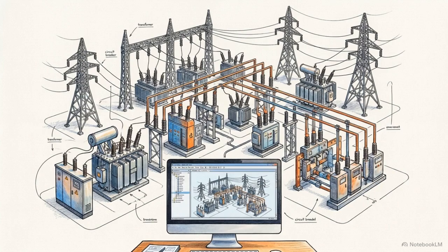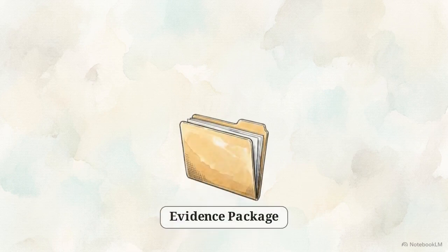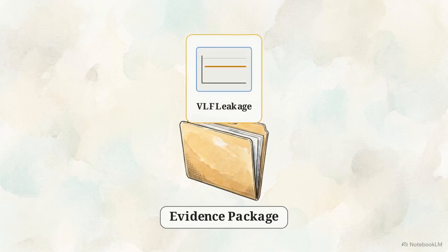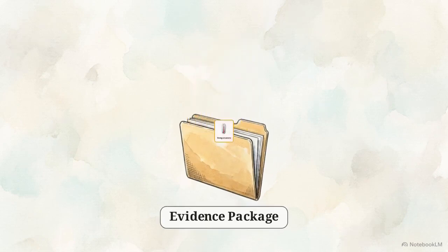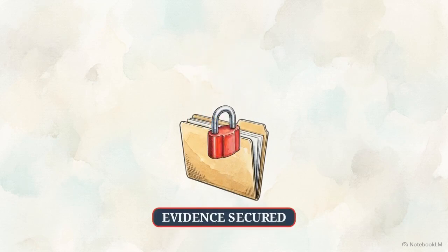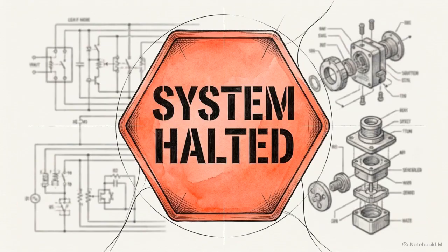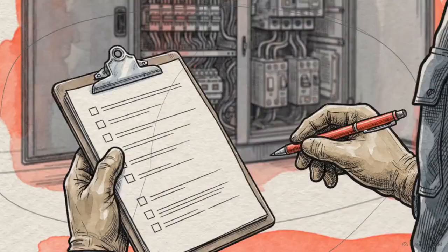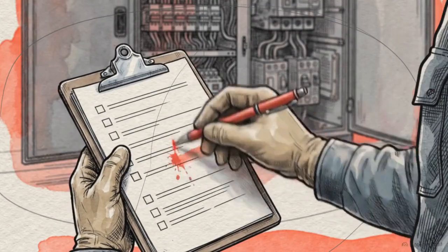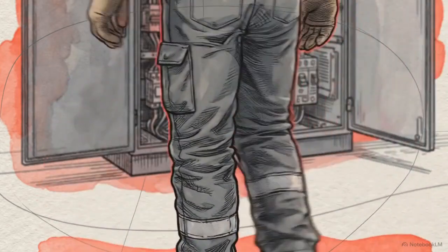Upon concluding Test 13.12, an extensive result and evidence package is compiled for handover. This package mandates the inclusion of all raw micro-ohm readings, VLF leakage trends, environmental temperature conversions, instrument calibration certificates, and formalized witness sign-offs. Regarding mechanical instructions for repairing a component that fails these tests, not specified in the provided sources, refer to project-specific hold point management. This lack of repair instruction is entirely intentional. Commissioning is a strict verification audit, not an assembly phase.